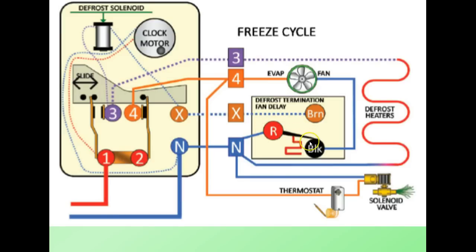115 volts into the evap fan motor. We do have a complete circuit through the defrost termination and fan delay. The fan is operating. We have 115 volts at the thermostat, passes through the thermostat, solenoid valve is activated, compressor is on, and we are now in the freeze cycle.